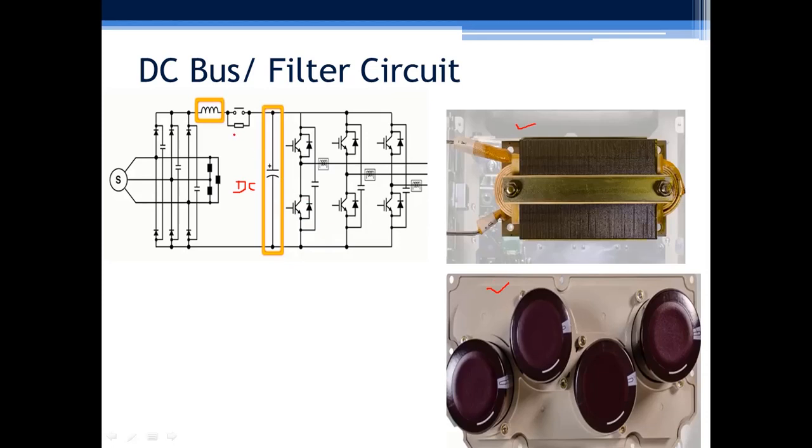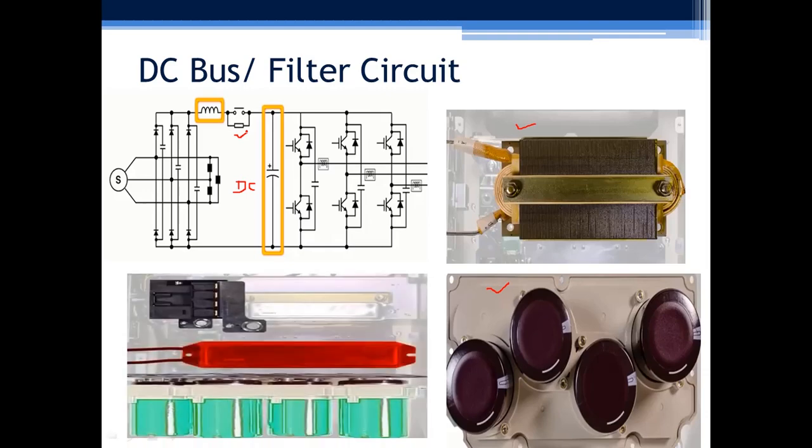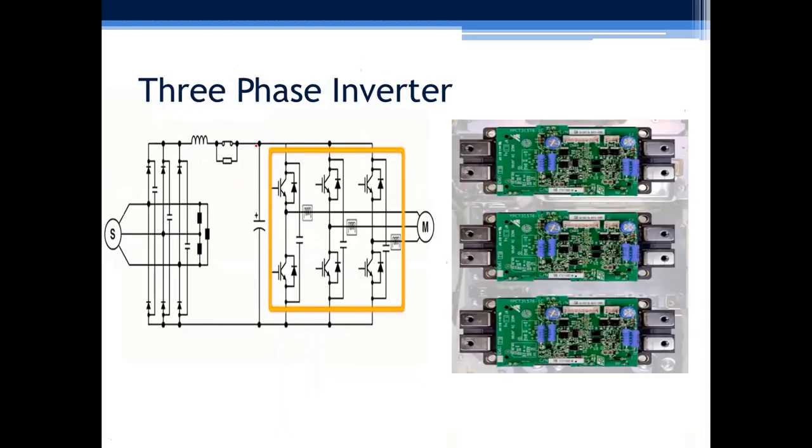Using a soft charger which consists of a resistor and a breaker circuit, you can charge it. When the capacitor is charged, this switch will act as an open switch and power is dissipated into this. So this will avoid overcharging of the capacitor. When the capacitor is not charged, this switch will act as a closed switch and it will keep on charging the capacitor. In this way, we can keep the DC link voltage constant, and this DC link will act as an input to the three-phase inverter.